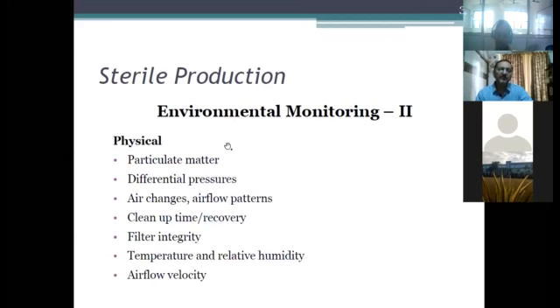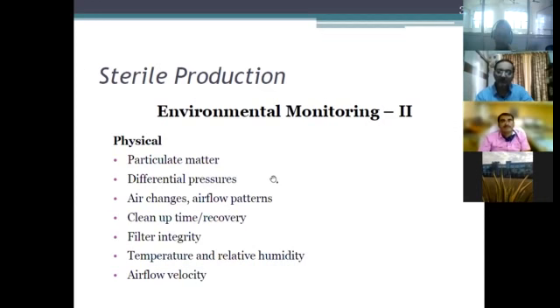Then physical, where we have particulate matter, differential pressures, air changes, airflow patterns, cleanup time, filter integrity, temperature and relative humidity, and airflow. These are the physical parameters in an aseptic area which have to be monitored. I do not know how many of you might have exposure to these parameters, how they are calculated in the industry, because you need to work in such areas, and then you are able to understand that.